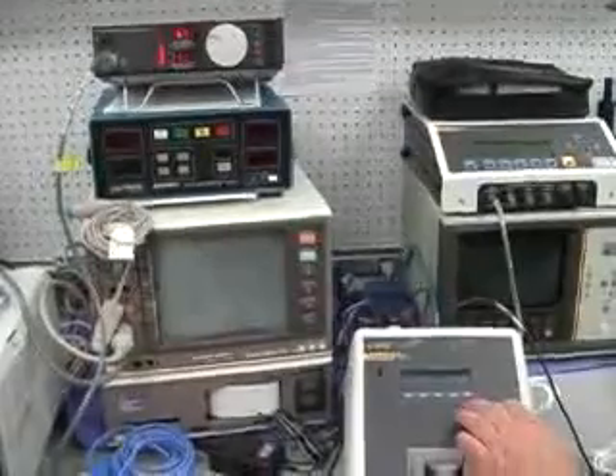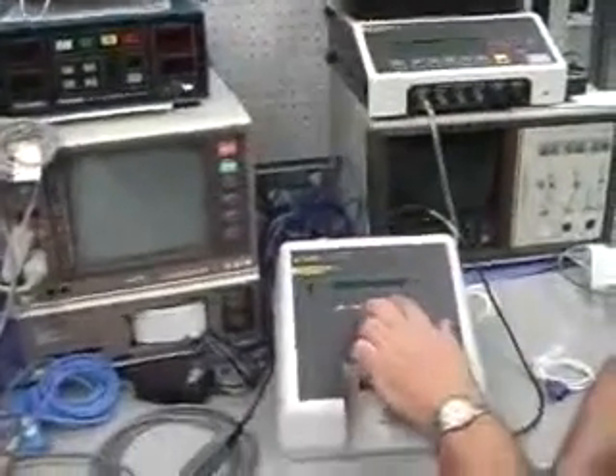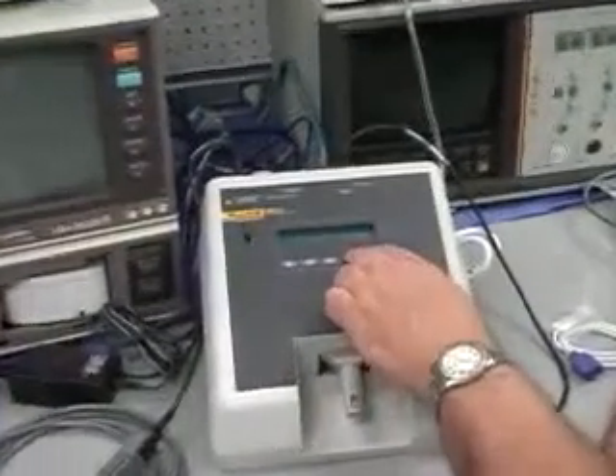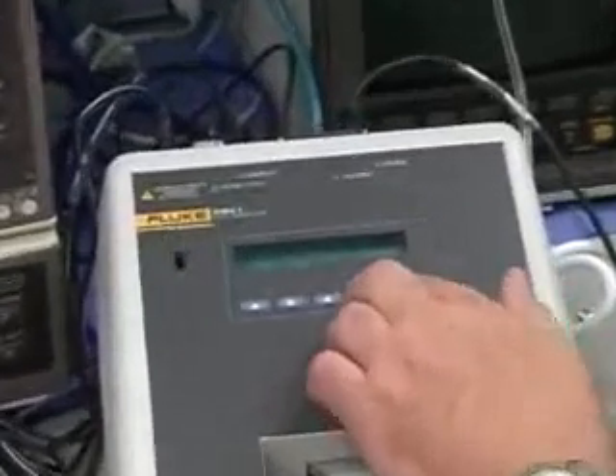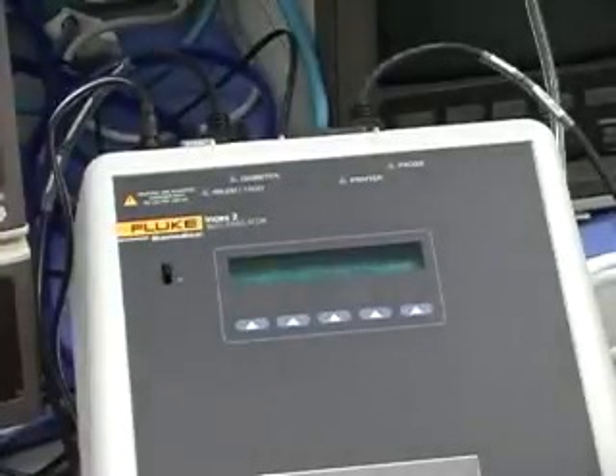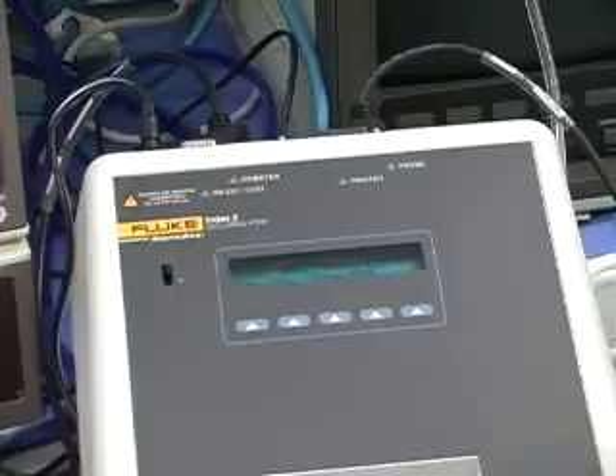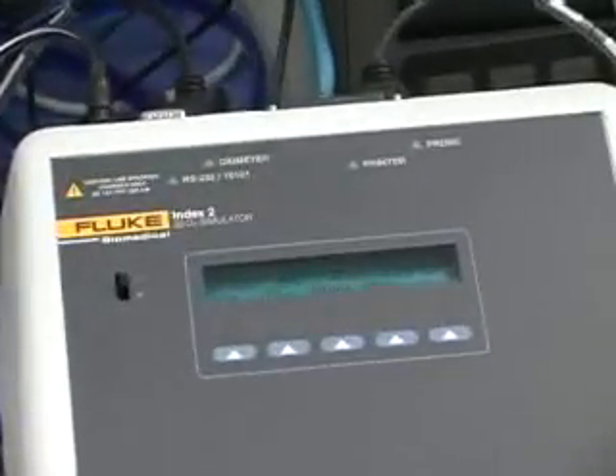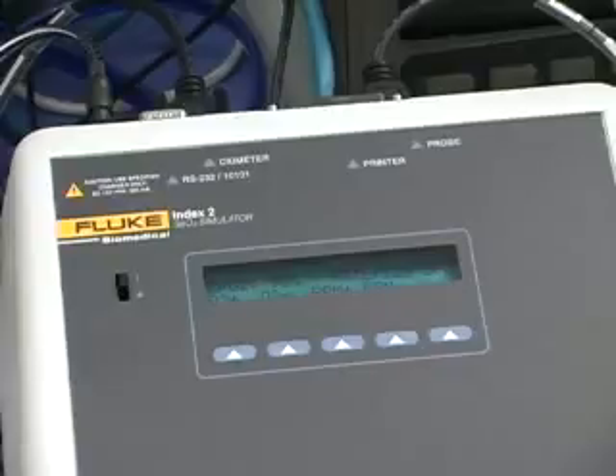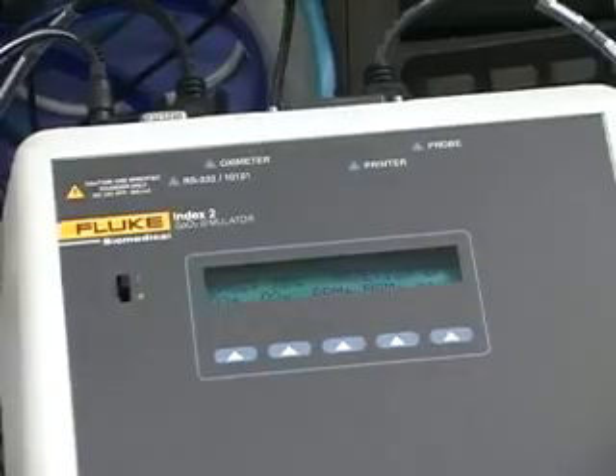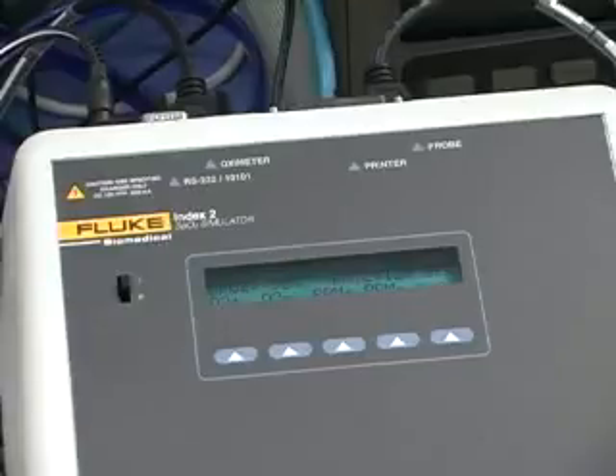And with the two, you're looking at very much a quick check on this thing. Pulse oximetry itself is an indirect, non-invasive measurement, where you aren't measuring the actual blood itself for oxygen saturation. You're looking at a secondary measurement, that of light going through both the pulsatile and non-pulsatile blood, and looking at the ability of this indirect method to give you a reading. So it won't be as accurate as the laboratory work, but obviously it's not as invasive to the patient. So applications are primarily for trending, looking for variation within the saturation of the patient on a long-term basis.